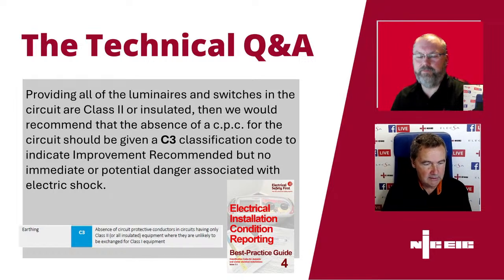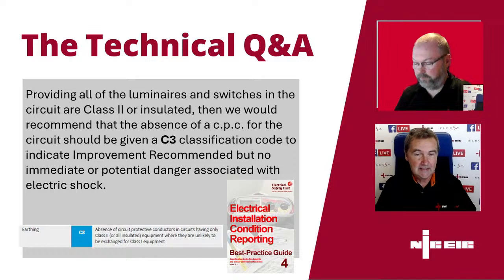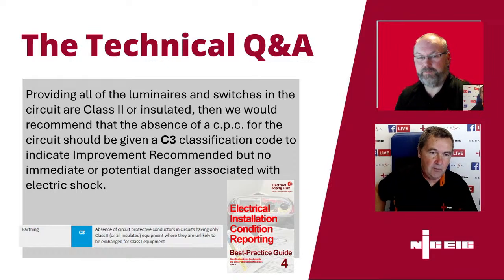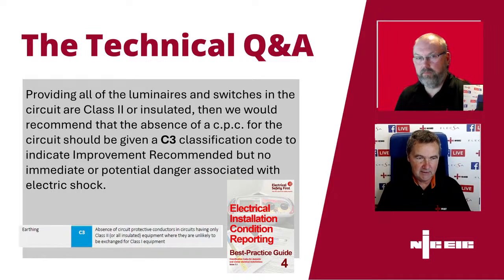It's all about this: we know the CPC would be there to provide earthing, typically for ADS, but without that, providing we've got Class 2 or insulated equipment, that's an alternative protective measure against electric shock. In a situation like that we'd recommend warning labels be added to consumer units or distribution boards to make people aware of the lack of CPC and warn them against exchanging Class 2 accessories for Class 1. The C3 is there to clearly show it's non-compliant with 7671, which requires a CPC at each and every point. However, due to the nature of the installation, although non-compliant, it's not considered unsafe for continued use, providing there's Class 2 or insulated equipment.